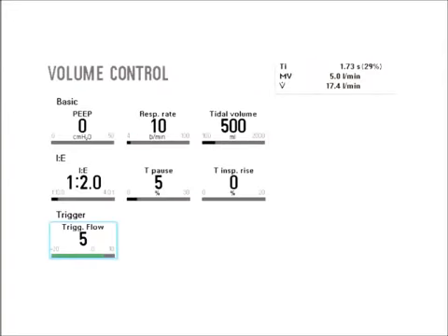Now, if we look at these ventilator settings, so I know I'm in volume control mode. It just states volume control. And as you notice, one of the settings, I'm just going to highlight it in orange, that I actually have a pause setting where I can set an inspiratory pause %.